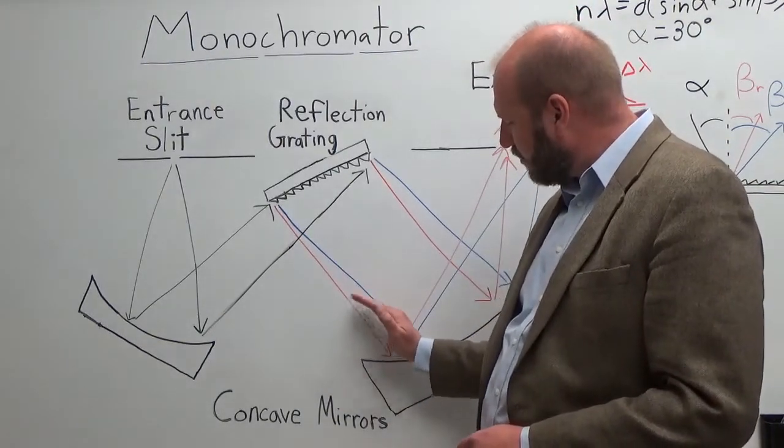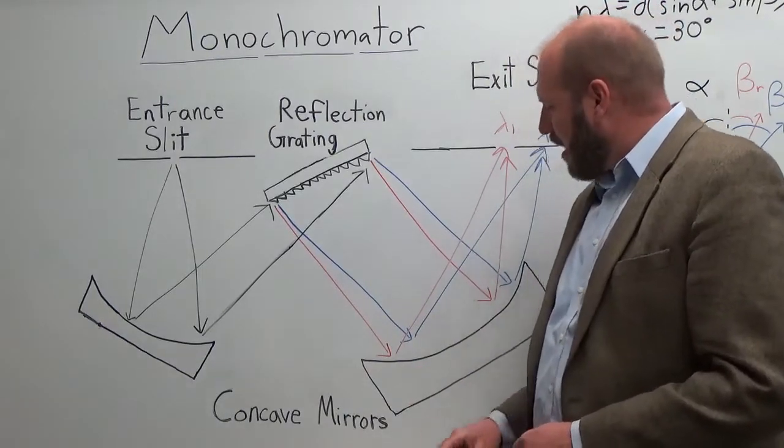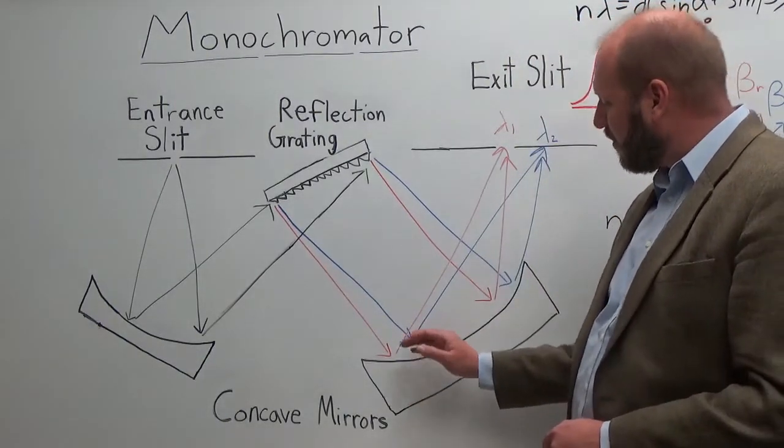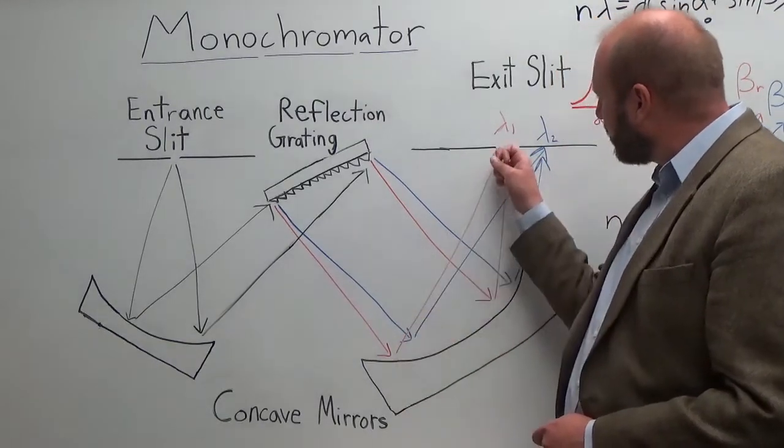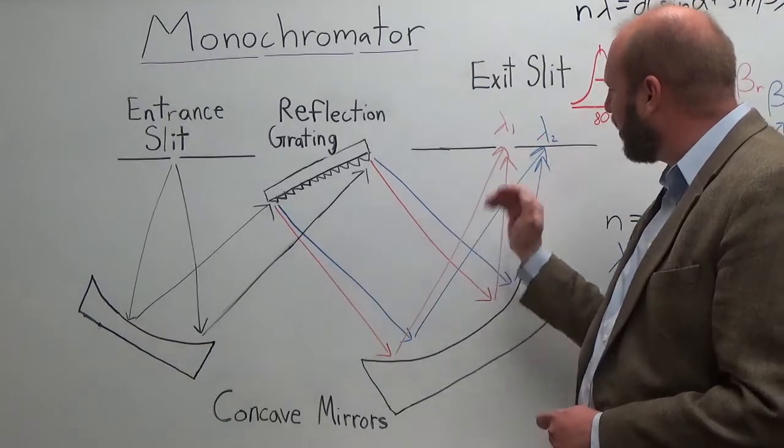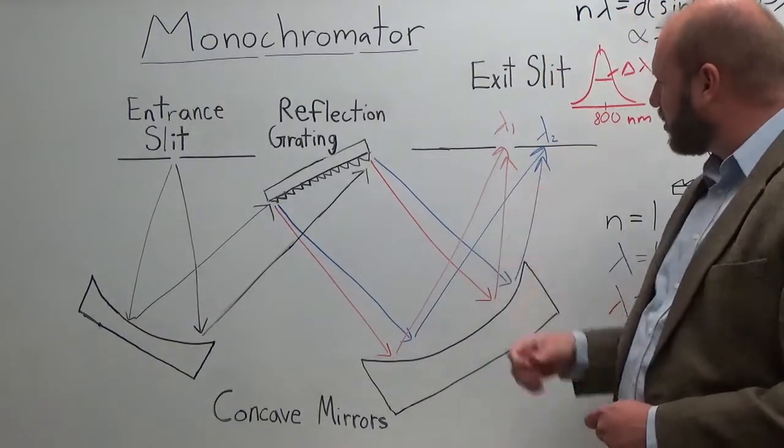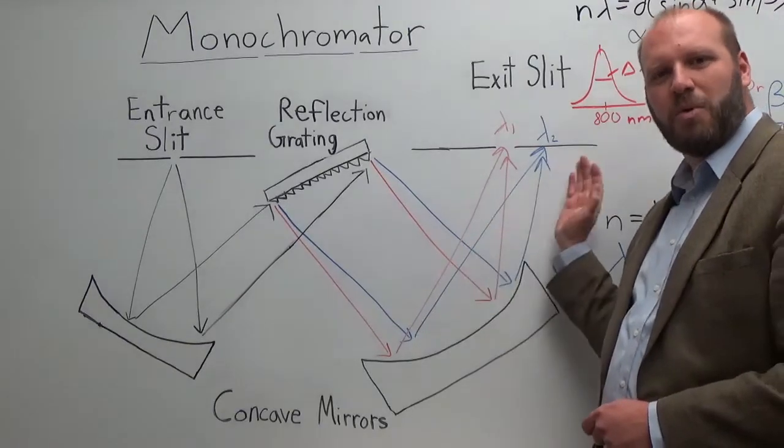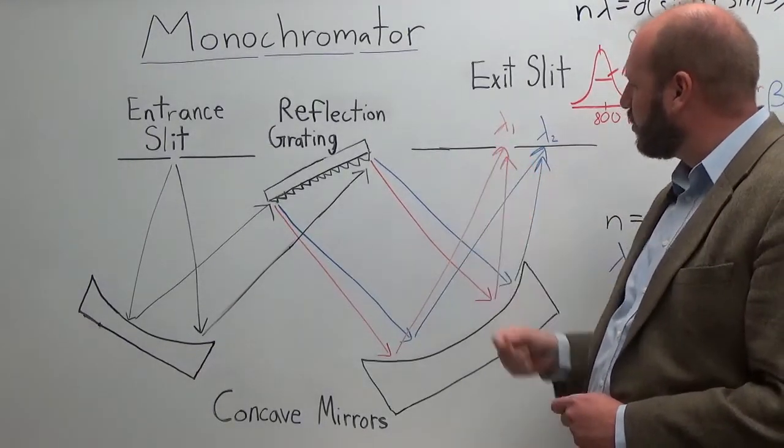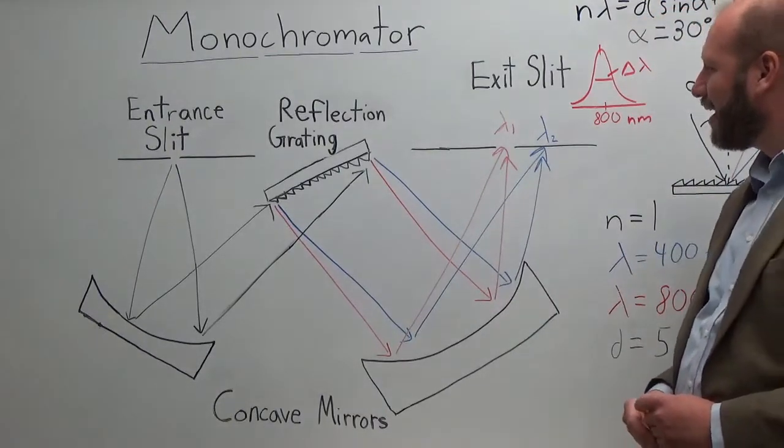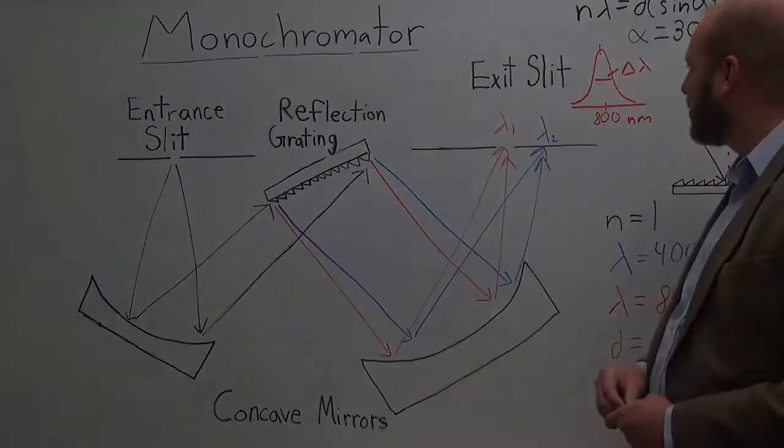So we have this spread of light that will then strike another mirror, a concave mirror. And this mirror's job is to focus the light onto an exit slit. Here the red light is going to be focused right at our exit slit so it will be allowed to come out of our monochromator. And our blue light is going to be focused to a different point. It's going to hit the wall and not exit our monochromator. So our exit slit will set a certain range of wavelengths that are allowed to exit. We then use this light to make our chemical measurement on the other side.